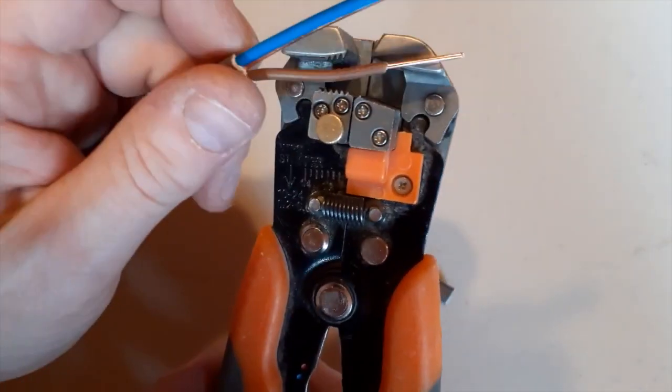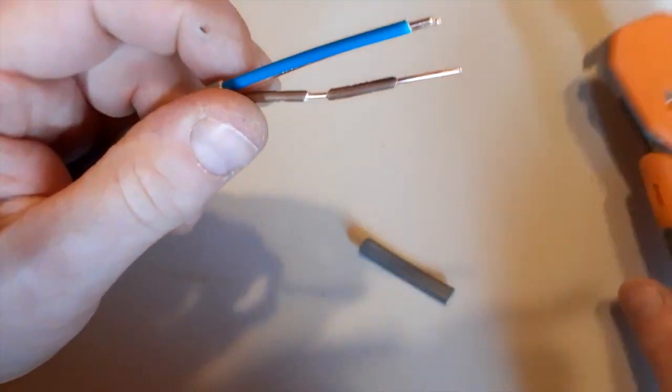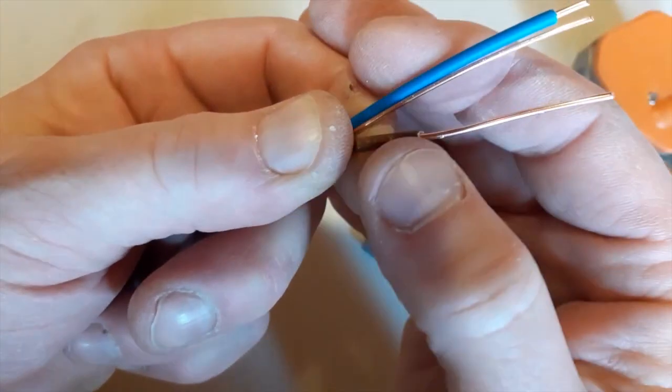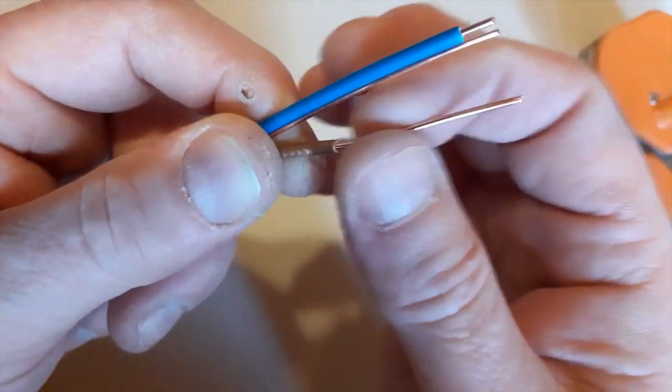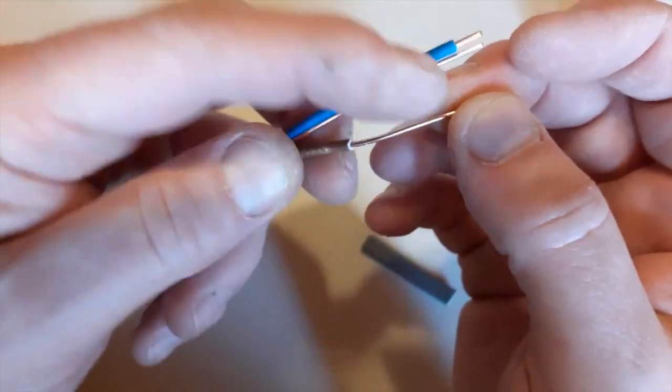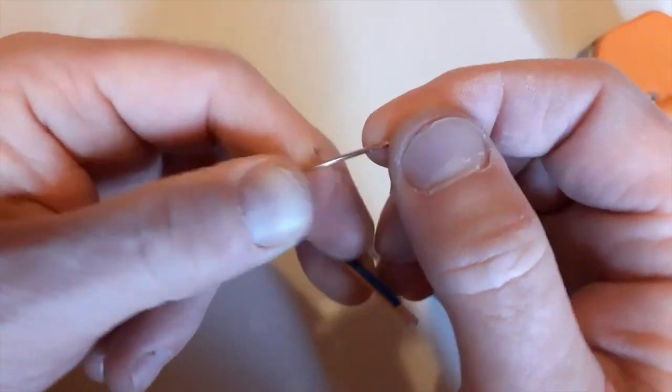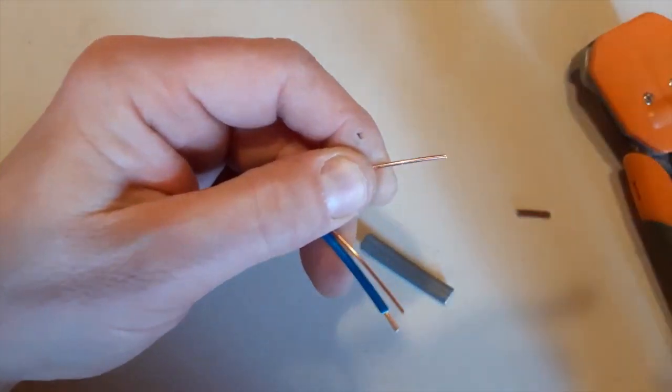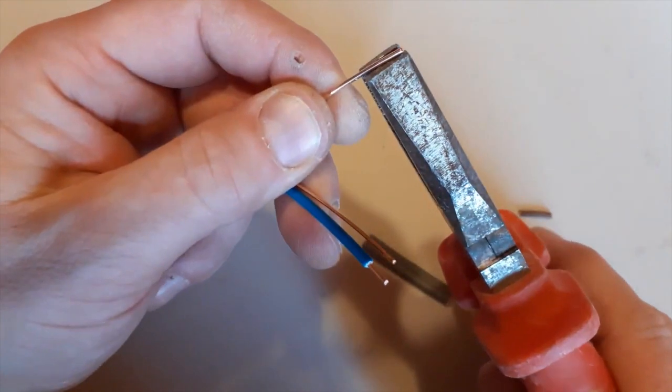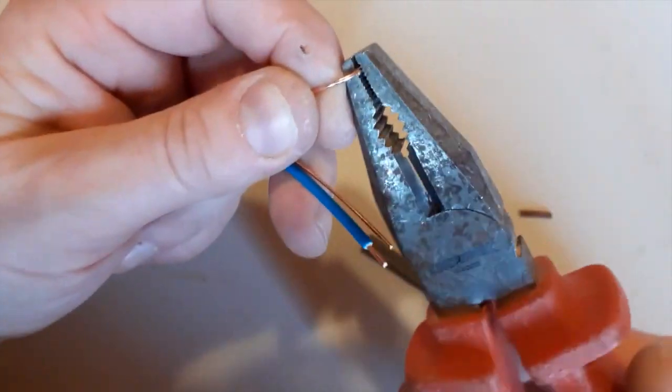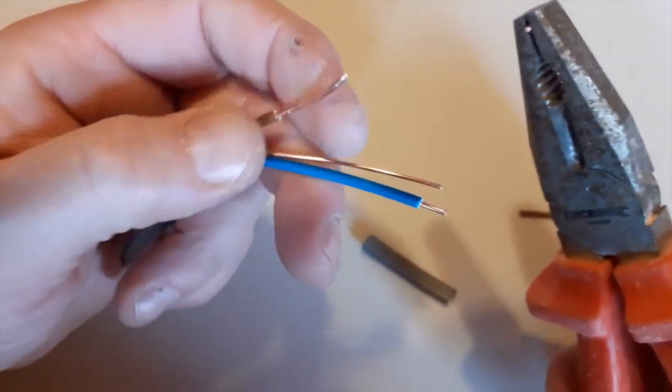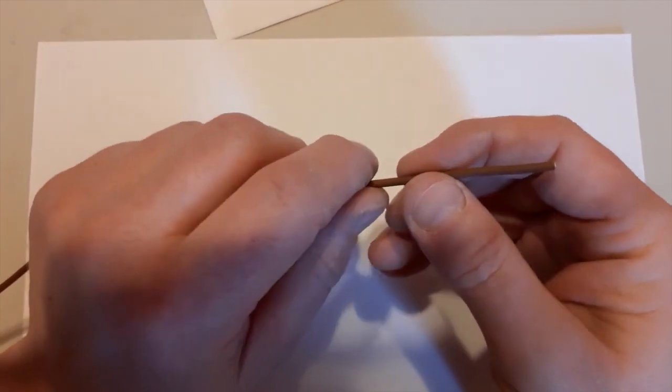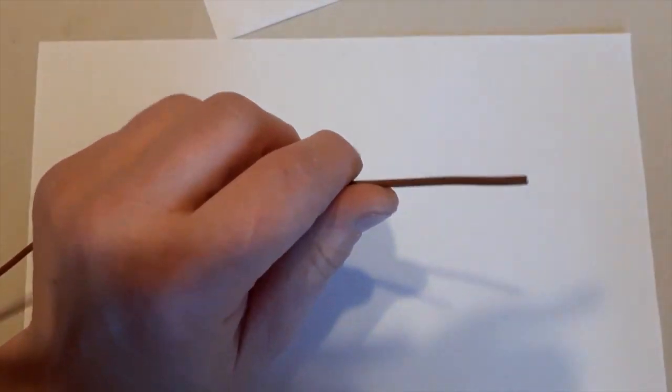There's a little dial on it to see how deep it cuts in, but you can feel it sometimes. It just catches on the copper and it can make quite a big chunk out of it. You can feel it with your finger, and that little ding, that little mark on the copper, it just weakens it. Let's have another go here. See how weak it is. One, two, three, four, five, six, seven, eight, nine. That went about nine there, so you can see the strength of the copper conductor is seriously weakened.